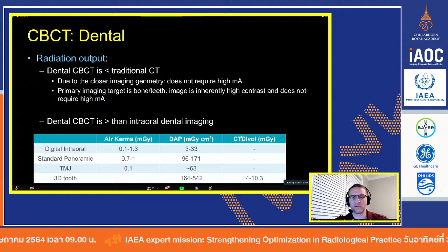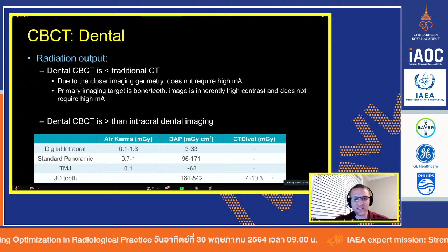So looking at air kerma values, you can see that the digital intraoral is usually about 0.1 to 1.3. So that is pretty low. The 0.1 is on the low end. 1.3 would be maybe if you're doing a molar or something more dense, so you just need a little bit more mA. Standard panoramic, once again, depends on the geometry and the size of the patient, but even the smaller patients that we image in our clinic will get about 0.7. So nearly 7 times that of the smallest intraoral, say an incisor.